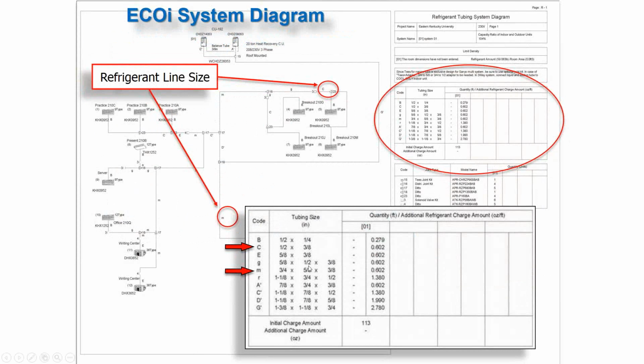Sometimes it'll tell us what size copper that needs to be. We can enter our distances of our piping runs. That'll help us to figure out how much additional refrigerant we need to add to a system, what our charge is going to be, and it will also allow us to see what our derate is, because the further we pipe away from the condensing unit, the indoor units, the less capacity we're going to be able to get from what it's rated at. So that's very, very important to see, and this software allows us to lay all that out so we can see it for design, all the front end work that we need to do.